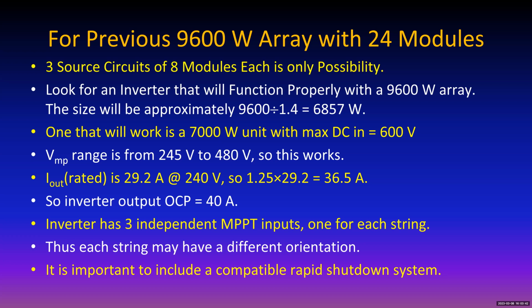One thing you can't forget is you need a rapid shutdown system, and there are lots of different options out there, but the nice thing about optimizers and microinverter systems is the rapid shutdown is built right into the optimizer and the microinverter. As soon as they see the utility is lost, which can be simulated by shutting off a switch that cuts off the utility feed from the PV system, the array thinks the utility's gone and it shuts down. That's a pretty convenient thing, but you can also do it with straight grid connect.